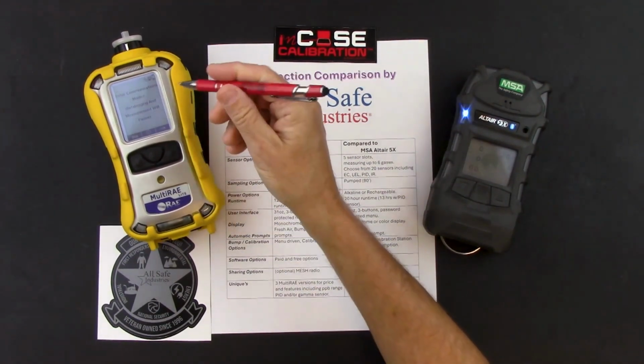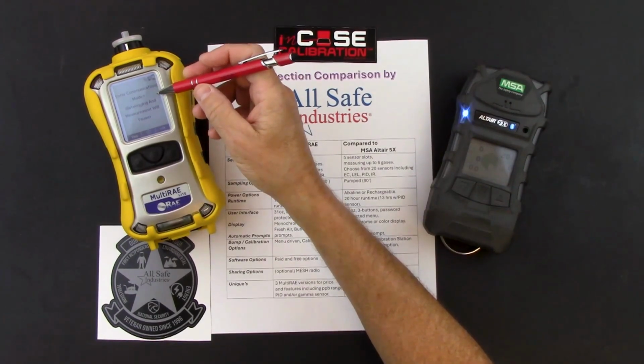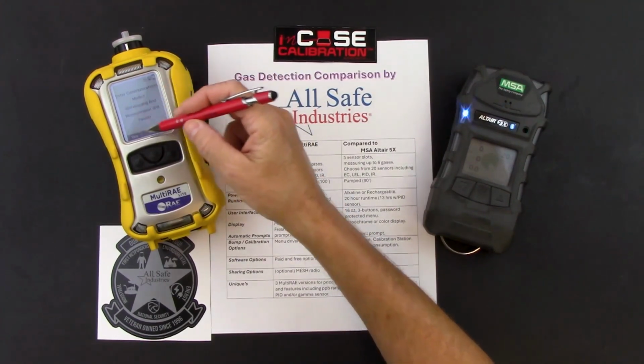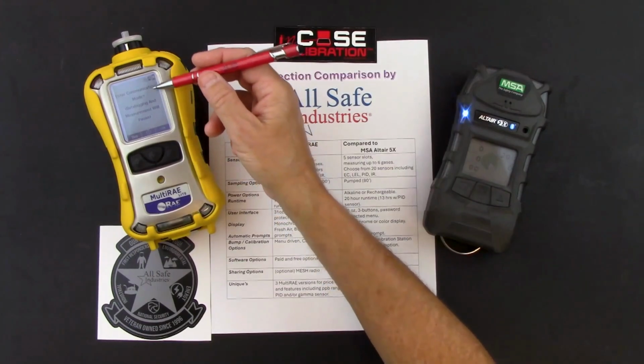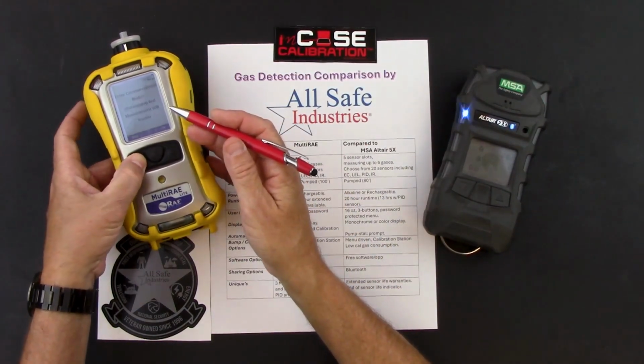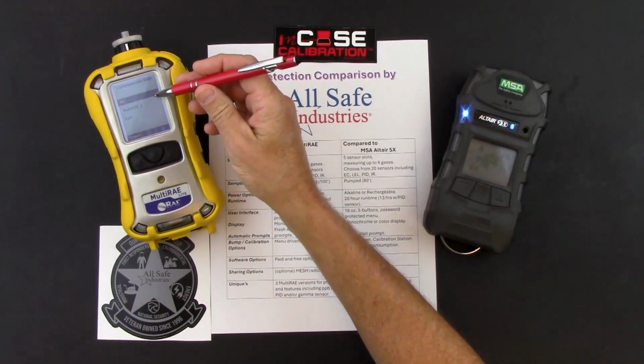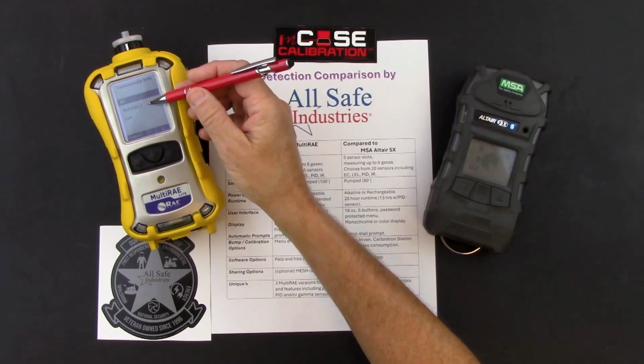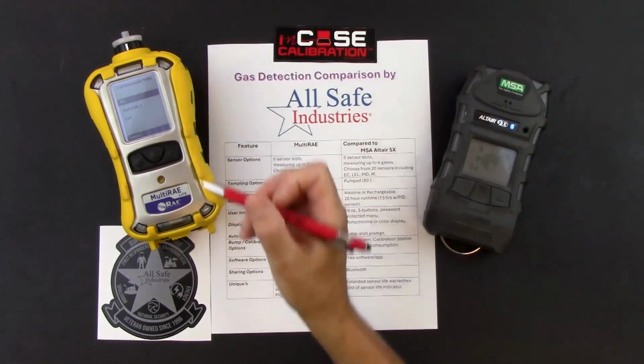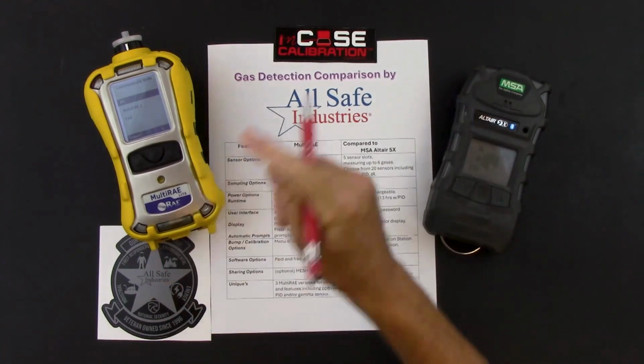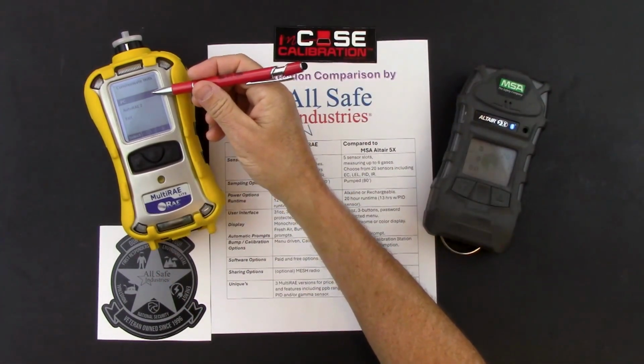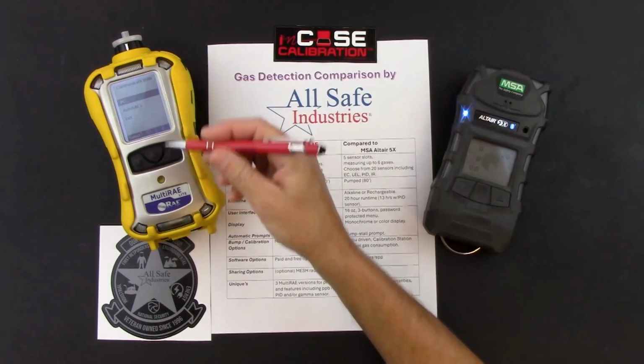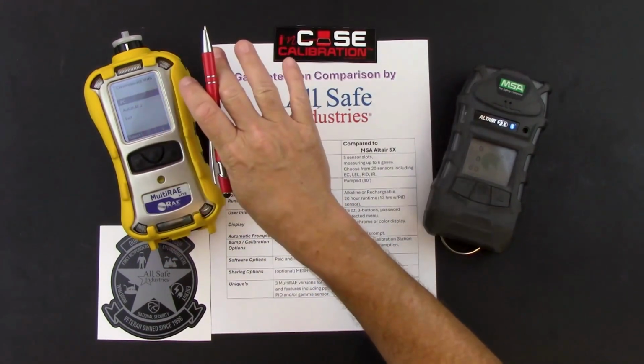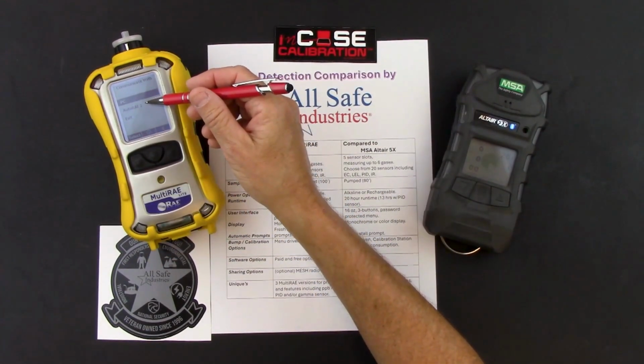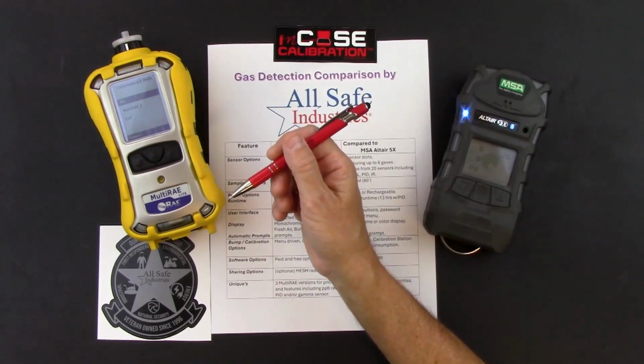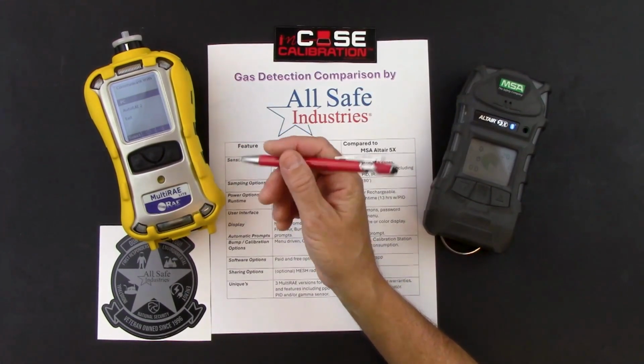And then the last page on a MultiRAE is the communications mode screen. It reminds me that my data logging and my measurement will pause if I enter this screen. So if I say yes, I have my choice of either communicating with a personal computer or the AutoRAE 2 calibration station. So I would use my travel charger with a cable over to my computer to connect to my computer and the software, or I can take the MultiRAE, put it in an AutoRAE 2 cradle for the MultiRAE, and run bump checks or calibrations right from that calibration station.